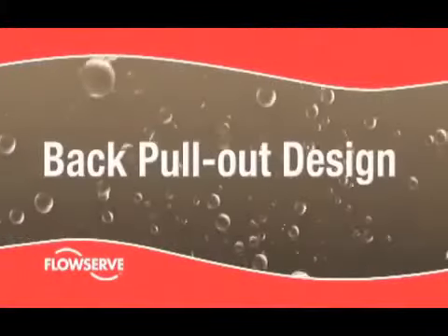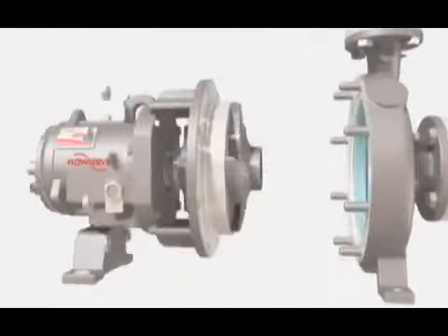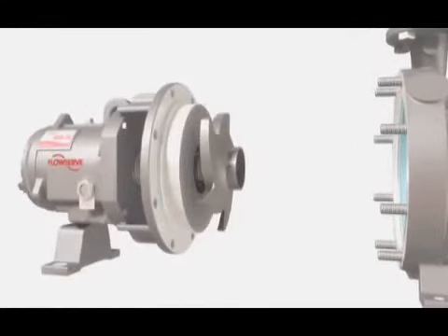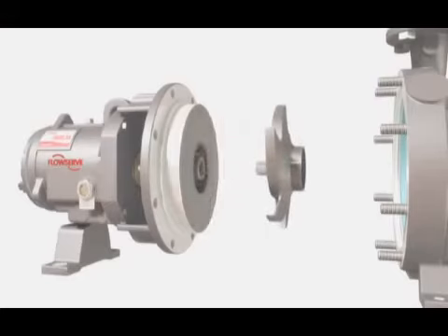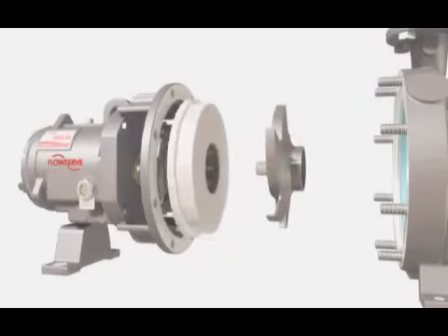Back pull-out design. The FlowServe Durco Mark III features a true back pull-out design. The casing remains in line, bolted to the suction and discharge piping. The remainder of the pump can be removed for repair or maintenance without breaking piping connections.